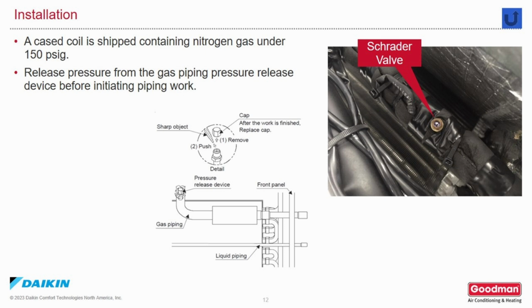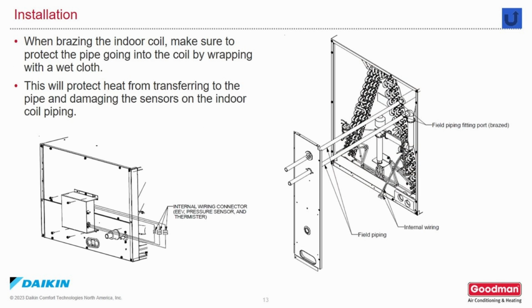Cased coils are shipped containing a nitrogen gas charge under 150 psi. Release the pressure from the gas piping pressure release device or Schrader valve before starting piping work. When brazing the indoor coil, make sure to protect the pipe going into the coil by wrapping it with a wet cloth or heat-absorbing paste. This will protect heat from transferring through the pipe and damaging the sensors on the indoor coil.